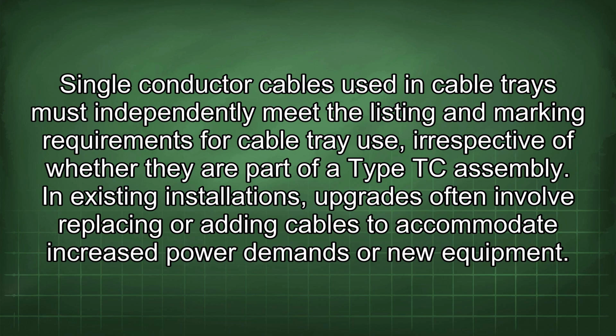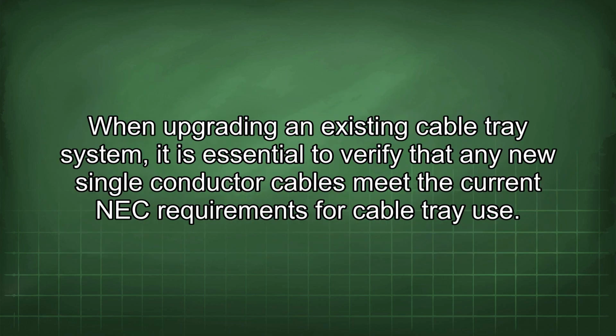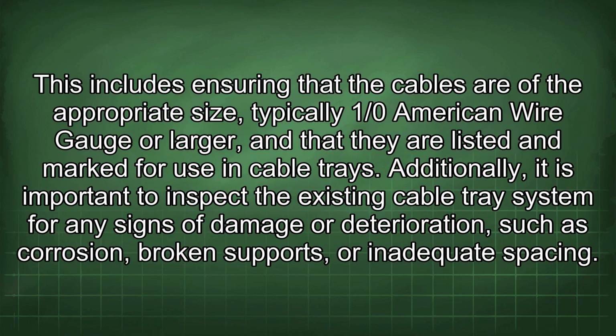In existing installations, upgrades often involve replacing or adding cables to accommodate increased power demands or new equipment. When upgrading an existing cable tray system, it is essential to verify that any new single conductor cables meet the current NEC requirements for cable tray use. This includes ensuring that the cables are of the appropriate size, typically 1/0 American wire gauge or larger, and that they are listed and marked for use in cable trays.